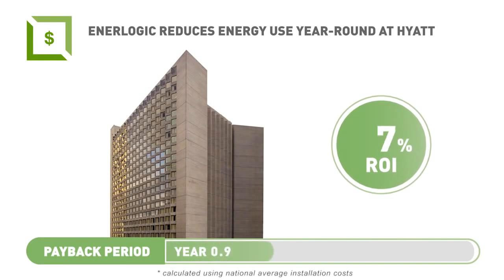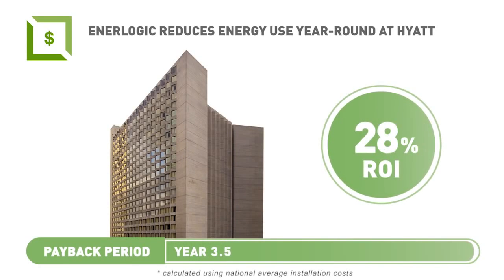The results show that in-room heating and cooling units for rooms with Enerlogic film used 23 percent less energy for cooling and 25 percent less energy for heating than the rooms without the film. These energy savings provided a payback on the hotel's investment in three and a half years, or a return on their investment of nearly 28 percent.